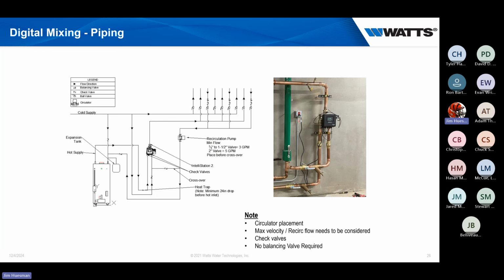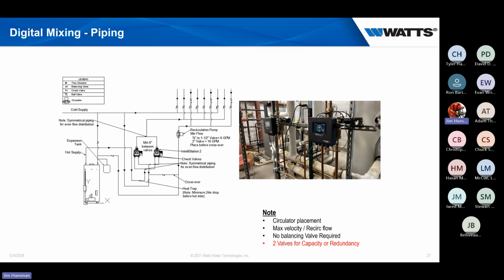So a lot of times what I'm doing is talking with you guys and the end users to start jumping into more of a dual system. Now I know you're thinking, Todd, you're being a salesman, just trying to sell two instead of one. But what I'll do is I won't add two 2-inch valves to the system. I'll actually drop these down and make them both 1-inch. So we'll have 1-inch in, 1.25 inch out. The reason I'm doing that is because I need to hit that 140.